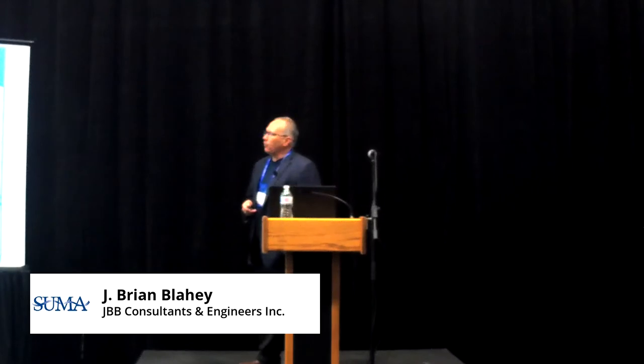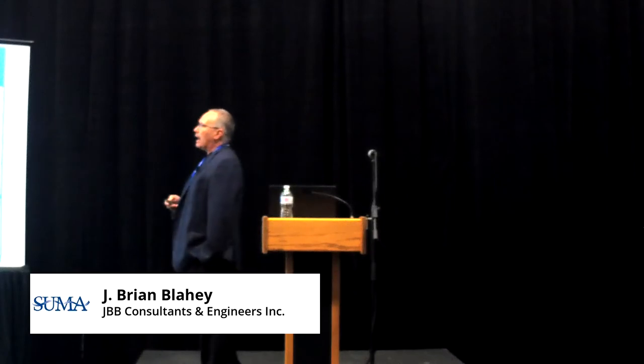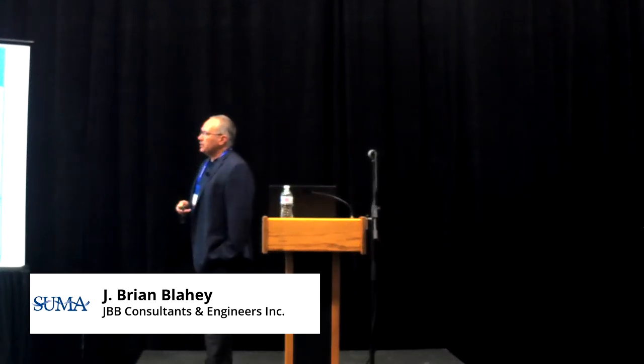Just to give you a little bit of a comparison, that's the reason R22 has been phased out as of January. R134A is about 1,300. R507, R404 were very popular, but they're also very, very high. R513 is a new blend. You can see it's a mixture of a bunch of refrigerants, fairly low. So it's got a few more years left, and those drop-ins are very high. R407C was popular for a while. Again, 1,774. These are very, very high numbers environmentally. And again, the natural refrigerants are 0 and 1. And those numbers mean that 1 pound of R22 is equivalent to 1,800 pounds of CO2.